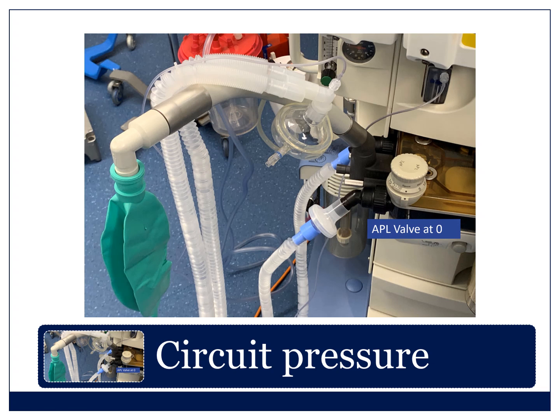Finally, this is the test I do in every single patient. You've got your circuit ready, the APL valve is at 0. That's normally how you start an anesthetic. I turn that APL valve to 20 or 30. I put my hand in front of that face mask, so I occlude the end of the circuit. I put the gas on so that the bag fills, and I squeeze the bag, and that's testing all sorts of things.